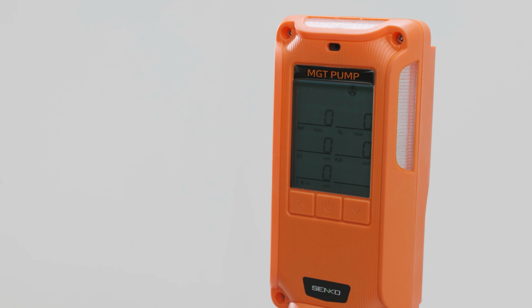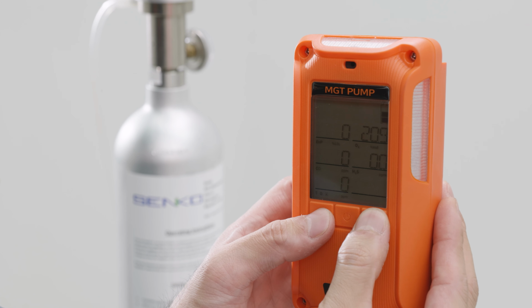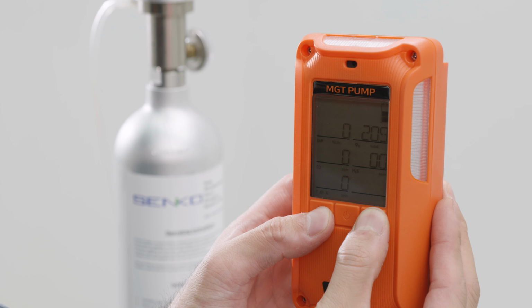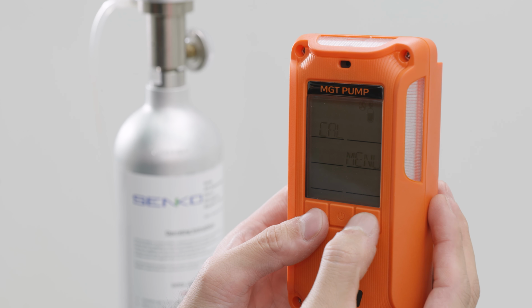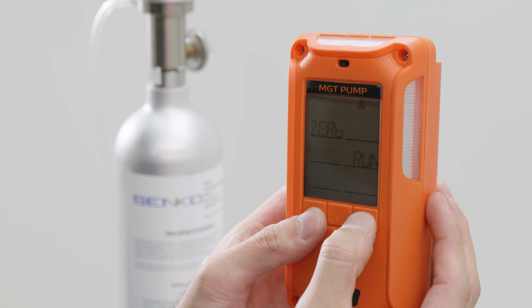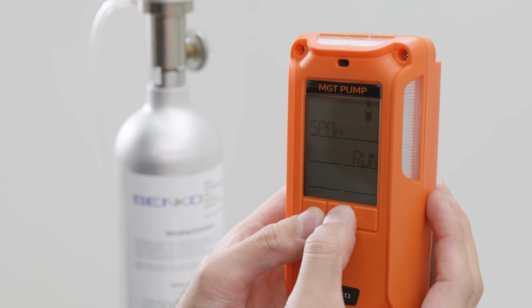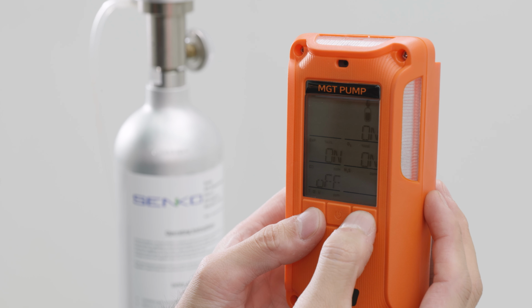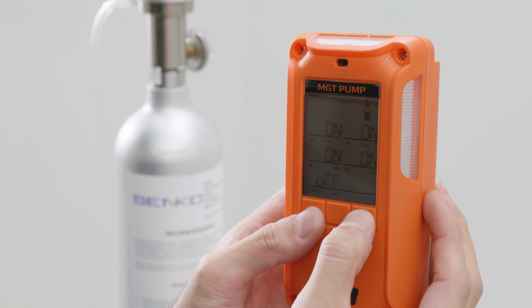When the countdown is complete, the calibration result is displayed as OK or FA. If FA appears repeatedly, sensor inspection or replacement may be required. Using a regulator and tubing, connect the calibration gas cylinder to the SP-MGTP.